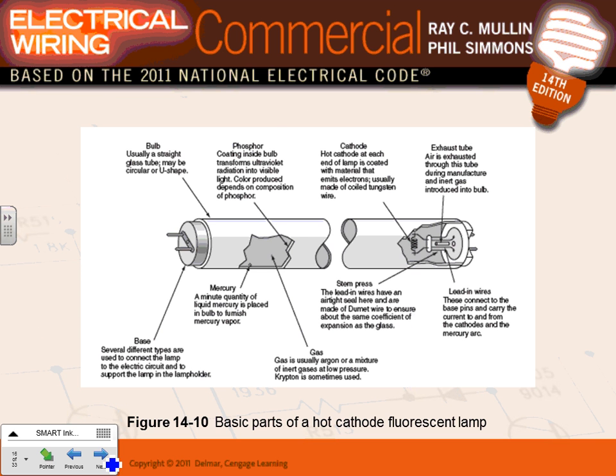They need a ballast. We'll talk about this one. Here's how they typically are, guys. You're going to bring the power in, let's just say the 120, brought here. You heat that filament. That filament starts shooting arc to the other electrode on the other side. In between, you hit the molecules of the mercury. You start your arc, and then that phosphorus material here will convert the light into a usable light. In plain English. Any comments?